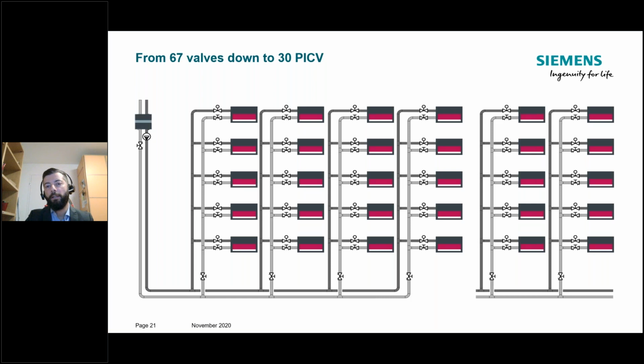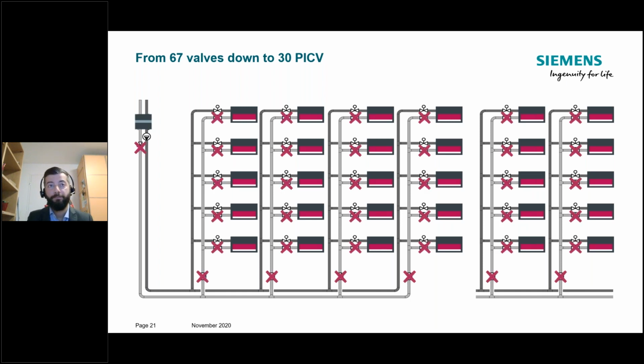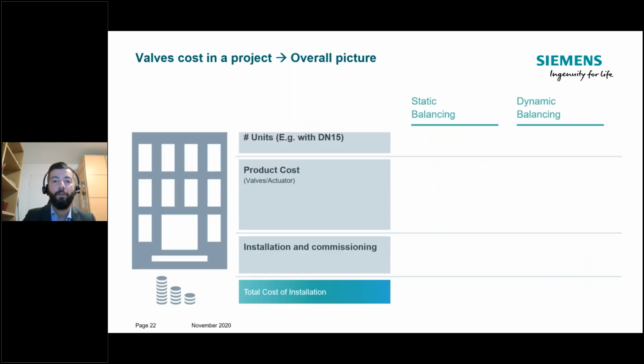And for the many of you that are familiar with PICV design, it is obvious to see that there is no longer need for a manual balancing valve in the system, because PICV is 3 valves in one. Therefore, you can eliminate any other control or balancing element. But not only, in fact, it is clearly much easier to balance a new or refurbished system, as there is no painful iteration along the coils of the whole building. So even the setup is much easier and quicker.